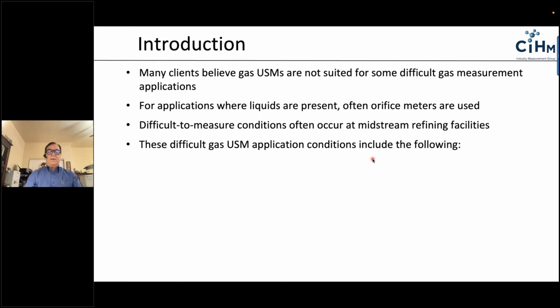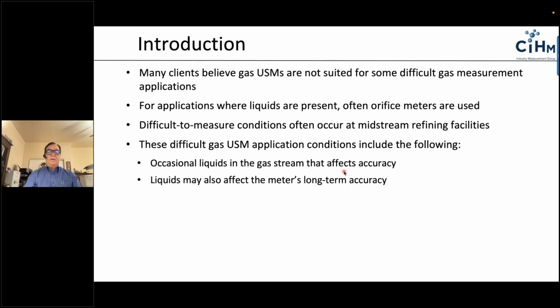These difficult gas application conditions include the following, and there are many others, but these are the ones we're going to cover today. Occasional liquids in the gas stream can affect, and will affect, the accuracy of any meter. Liquids also affect the meter's long-term accuracy. So we're going to talk about what happens if your ultrasonic meter gets subjected to liquids, and answer the question: is there going to be an effect on the long-term performance of the meter? Regulator noise has long been known to be an issue with ultrasonic meters. We didn't know this in the 90s, but we found out about it. So we'll talk about dealing with ultrasonic noise from regulators.